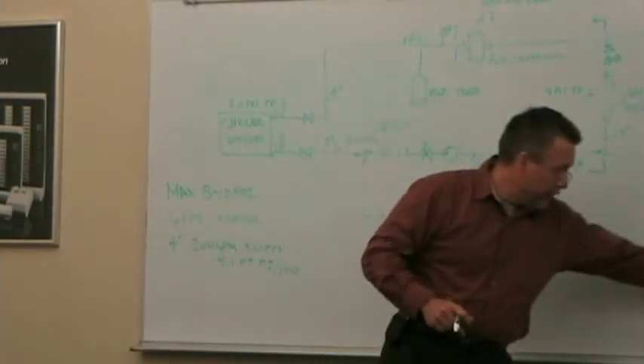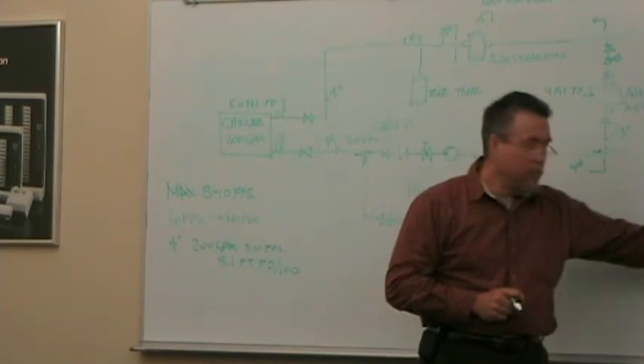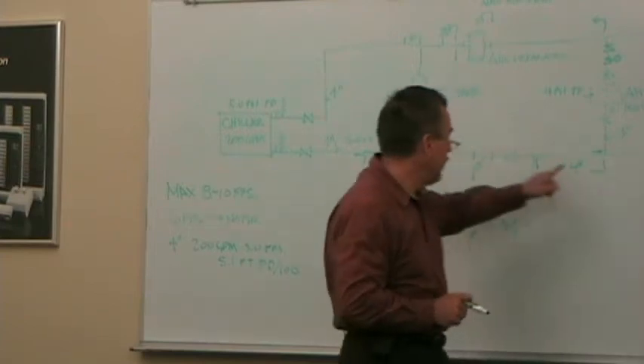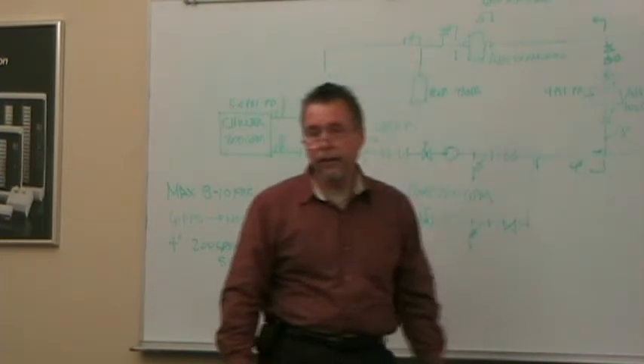Just say 15 feet. So now you've got to start thinking: I've got 300 feet of pipe, and the pressure drop of that 300 feet of pipe is 15 feet. One globe valve is 120 feet. One check valve is 28 feet. One check valve is greater than my pressure loss from here all the way to here. And let's look at elbows.